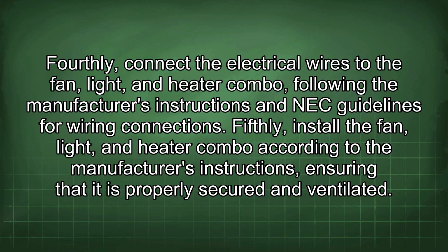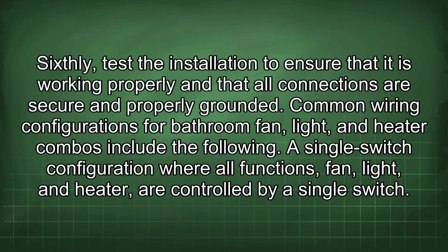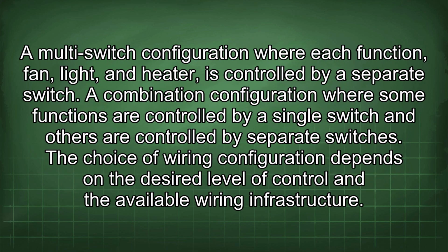Fifthly, install the fan, light, and heater combo according to the manufacturer's instructions, ensuring that it is properly secured and ventilated. Sixthly, test the installation to ensure that it is working properly and that all connections are secure and properly grounded. Common wiring configurations for bathroom fan, light, and heater combos include the following. A single switch configuration where all functions, fan, light, and heater, are controlled by a single switch. A multi-switch configuration where each function, fan, light, and heater, is controlled by a separate switch. A combination configuration where some functions are controlled by a single switch and others are controlled by separate switches. The choice of wiring configuration depends on the desired level of control and the available wiring infrastructure.